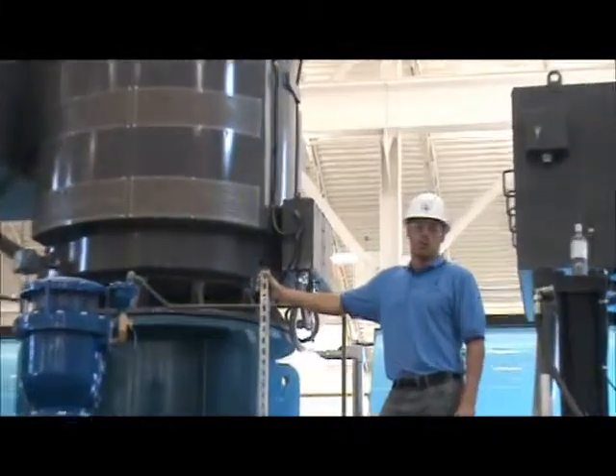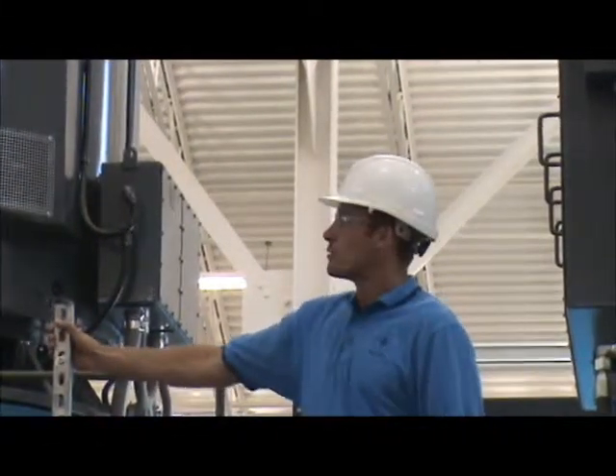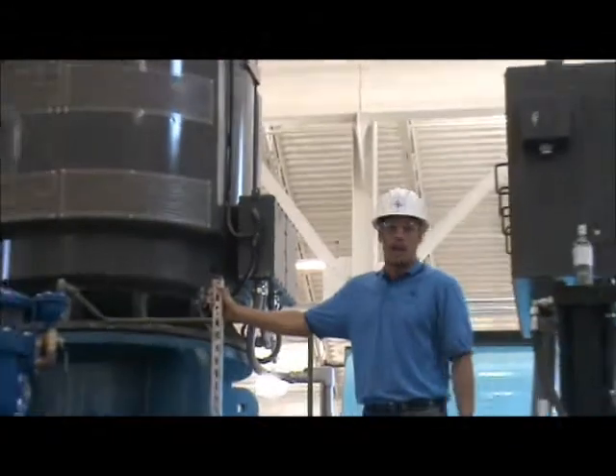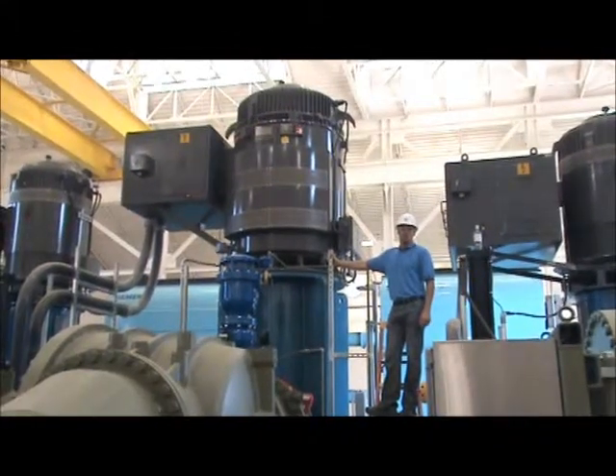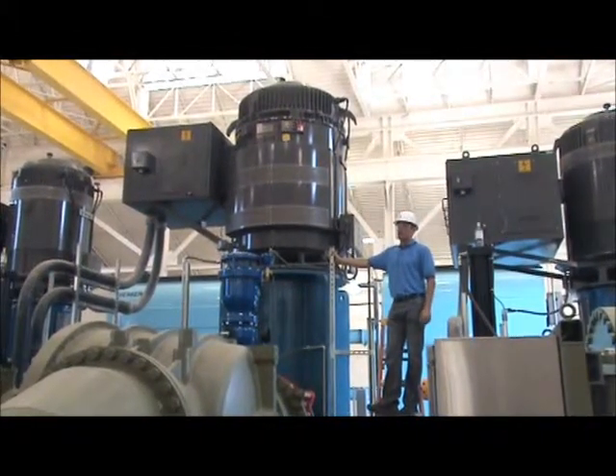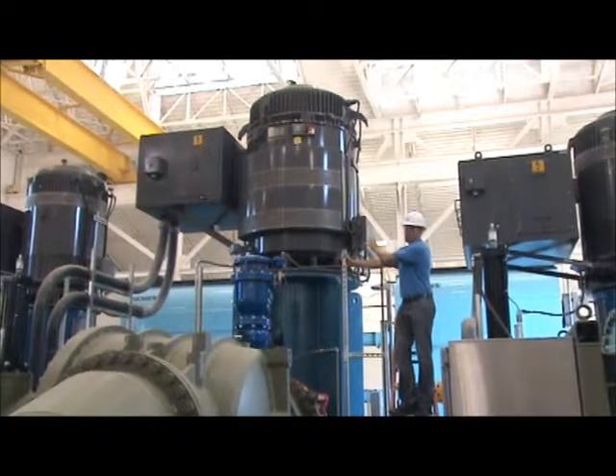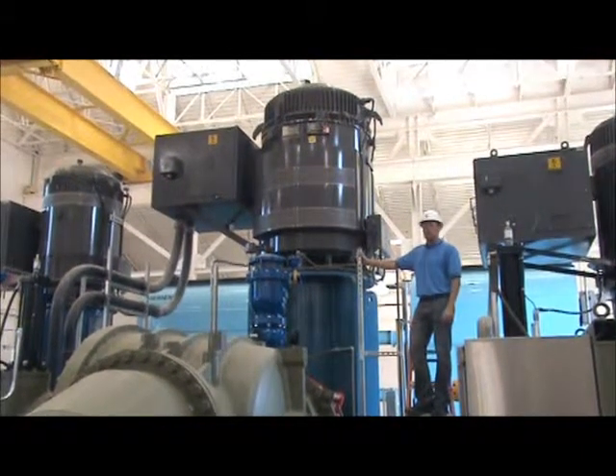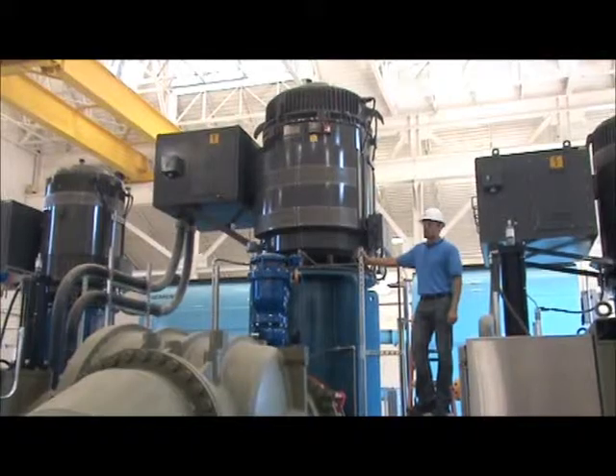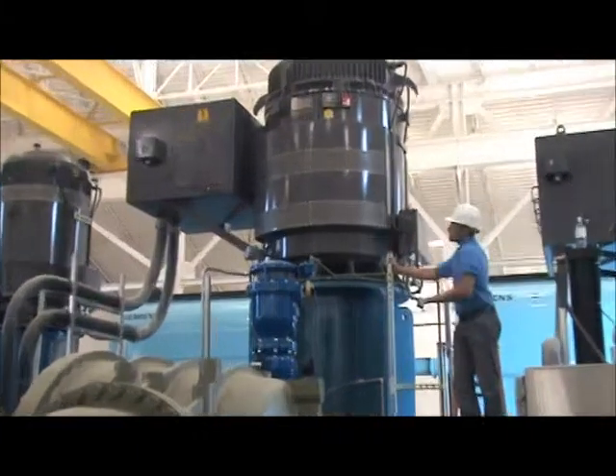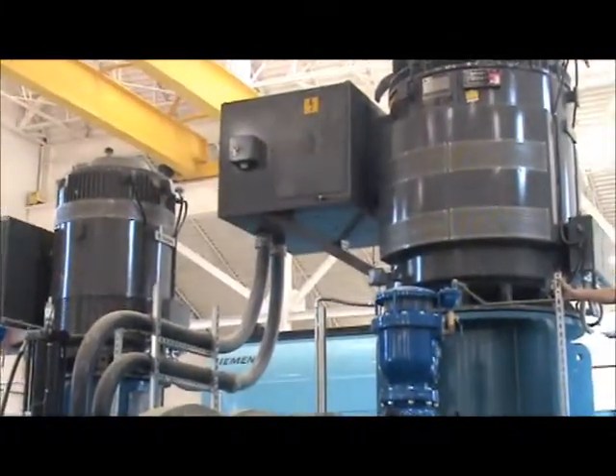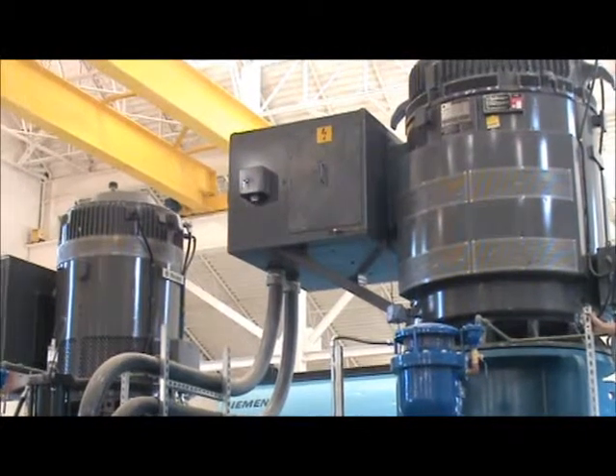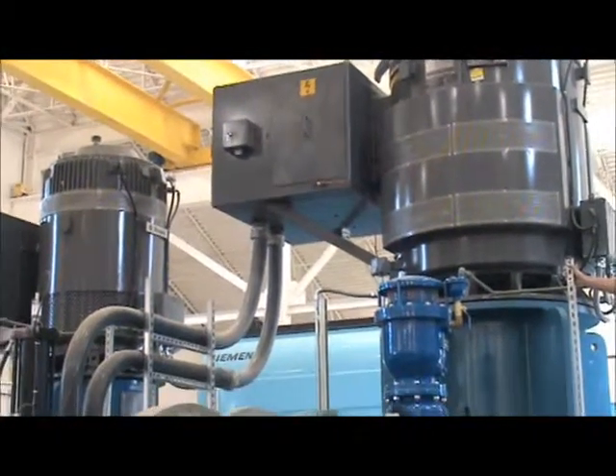I'd like to give you a tour of the equipment that we're controlling. We'll start with the motors. They're 1,000 horsepower, 4160 volts, and 900 RPMs. This one has a dual winding, so we can go into a low speed mode. On the far side, it houses the terminal connections for the power, as well as surge arresters.